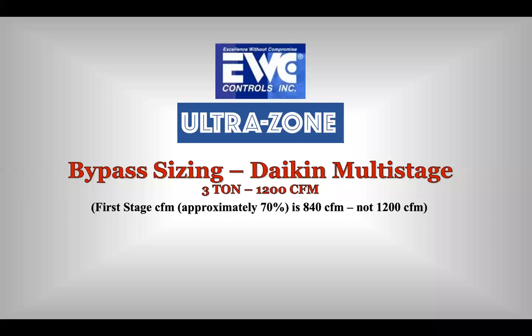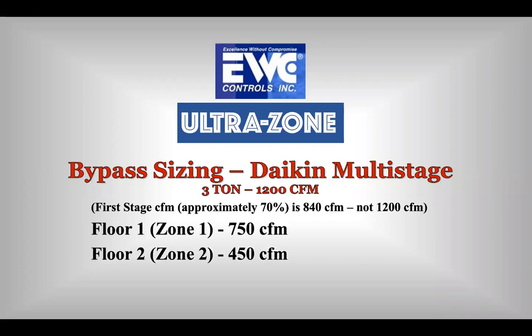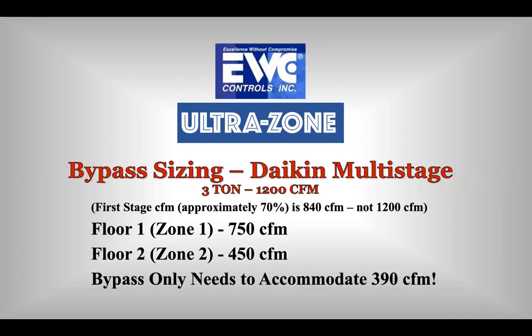So let's stay with the program. I'm looking at 70%, or I'm looking at 840 CFM as my total in my bypass figure now. 750, my 450. Now I only need to accommodate 390 CFM. Remember, we had talked about minimizing the need for bypass. We did not talk about eliminating bypass.